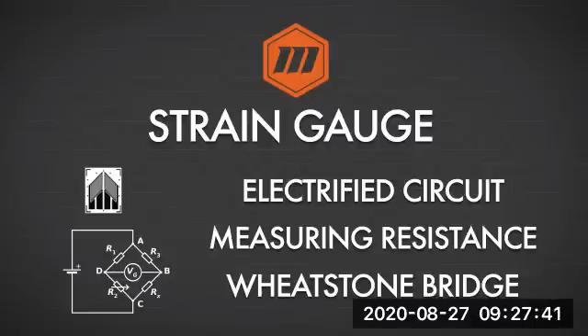The strain gauge is laminated to our substrate. It could be glued, or in other cases where those gauges are used, they could be welded. Once that is fixed to its substrate, any torsional change or flex within the strain gauge produces a voltage change due to resistance that we can measure. If we use the Wheatstone bridge, it allows us to take the voltage, see what the resistance is from that, and then correlate that to the flex or torsion within the link or element that's being tested.